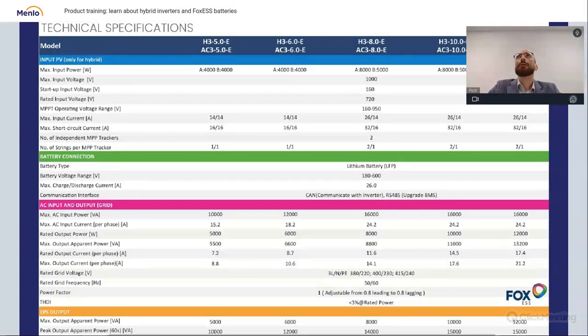Those units use RS485 communication or CAN communication. Generally, if you want to talk with this unit, you can use Modbus or any appliance that can output a Modbus translated message to the unit. Perhaps you have some smart grid or smart home device that operates your home energy management system. You can easily add this inverter to output information about the system to your HEMS, smart grid, or smart home device.